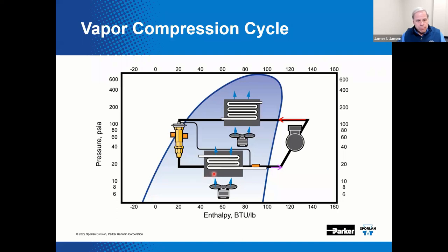And then here, the evaporator, where the heat removal process begins while the refrigerant changes state to a vapor and the low temperature saturated refrigerant liquid boils, removing heat from whatever you want to cool, chill, or freeze, only to re-enter the compressor and start the process all over. In addition to these four primary components, the system includes the refrigerant, lubricant, and all the interconnecting tubing or piping.